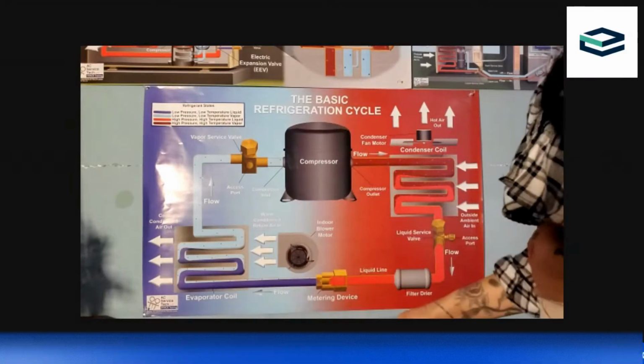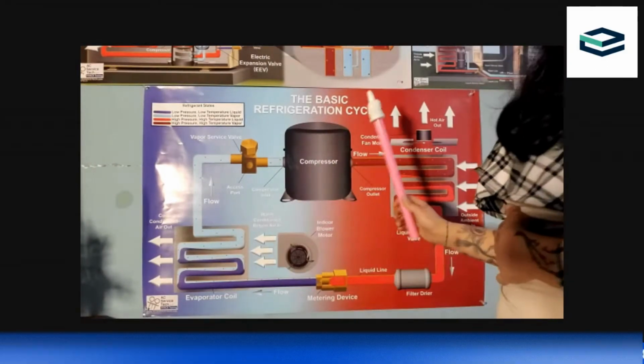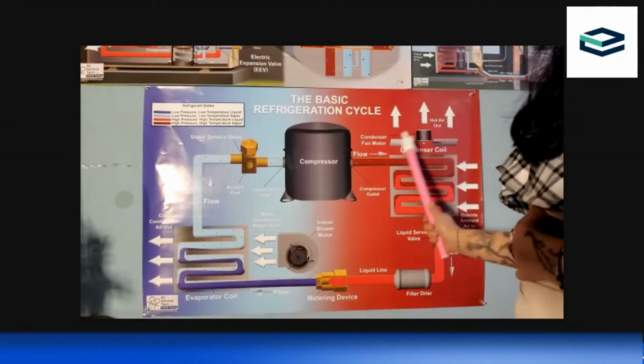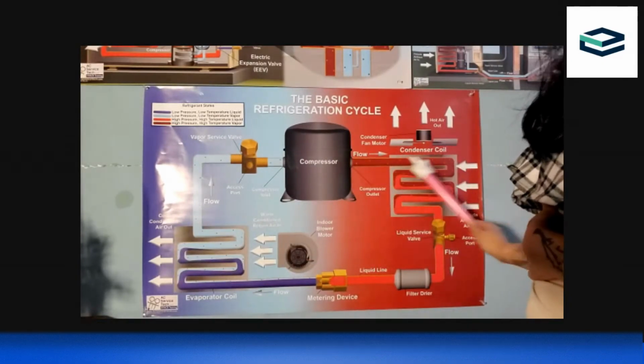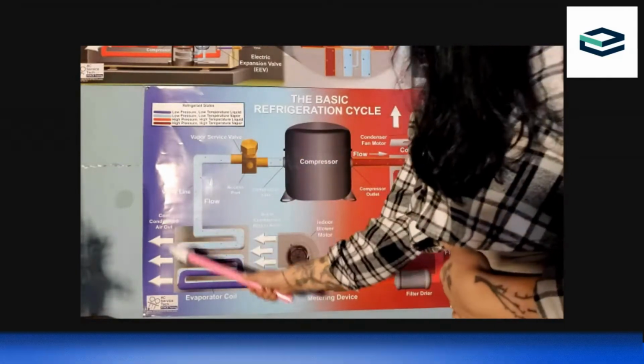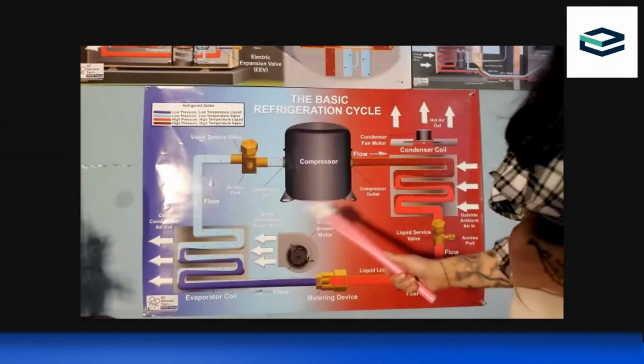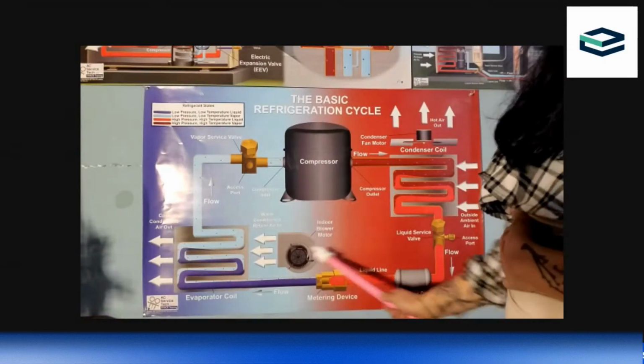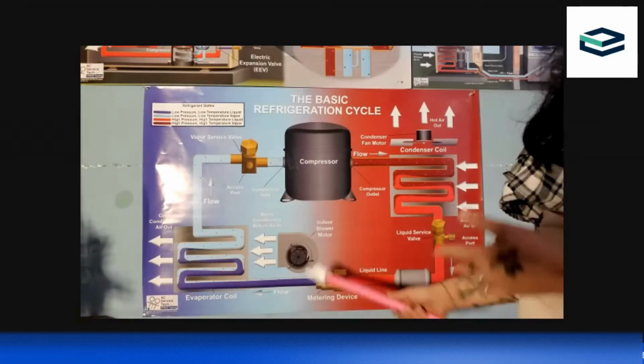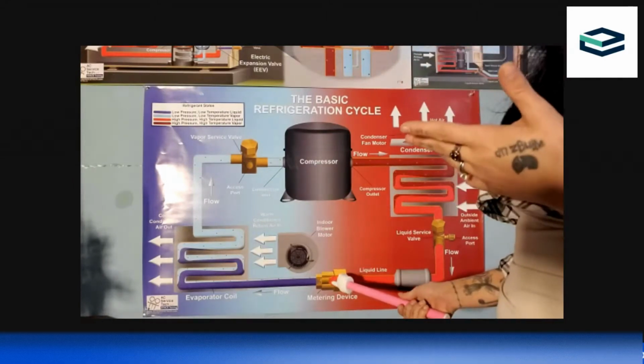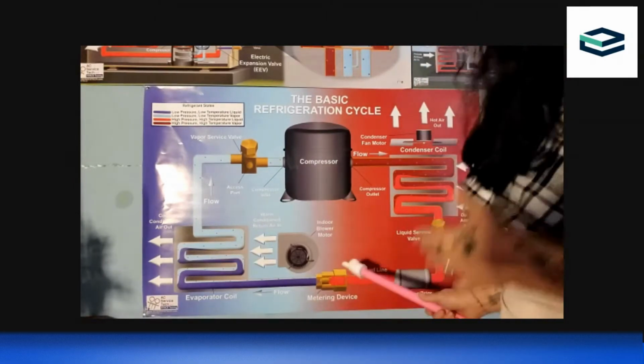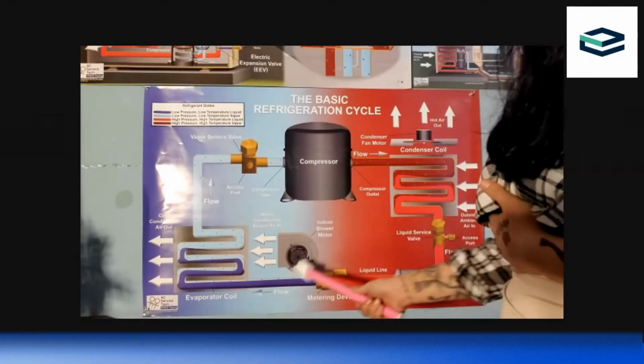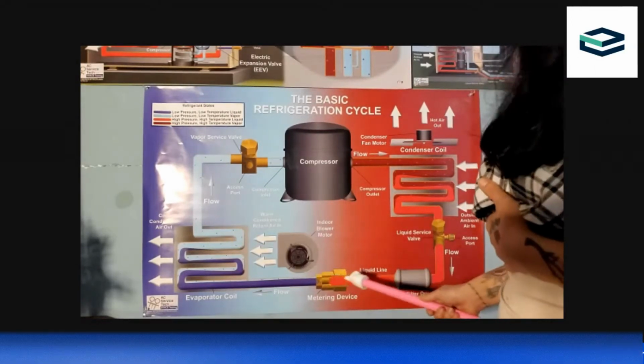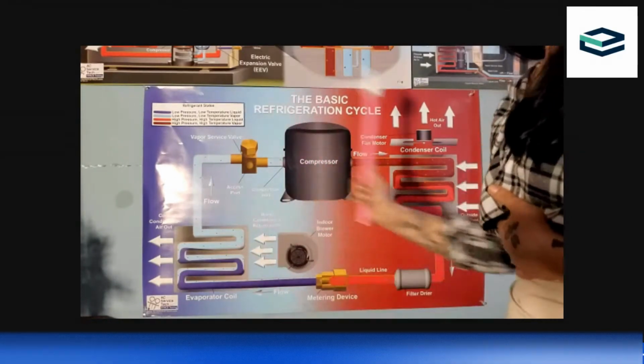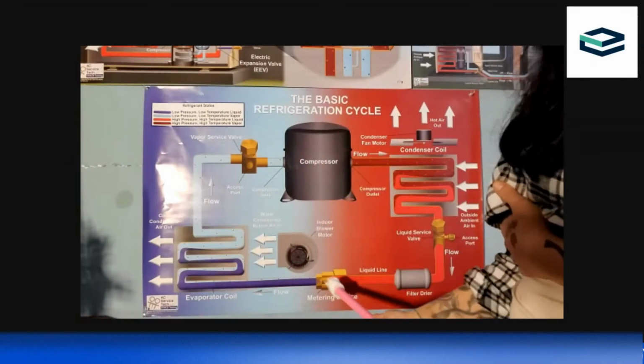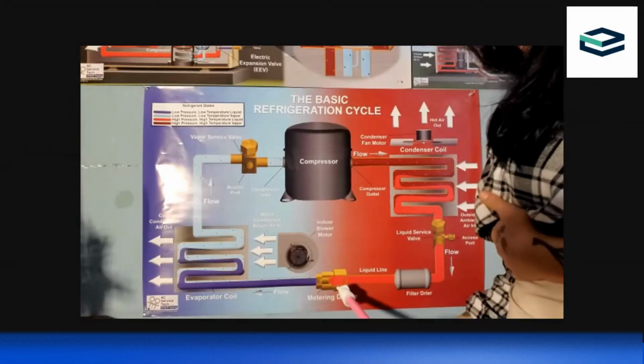So those are important. If we have a very, very high liquid or very, very low liquid saturation, we could have too much liquid in one side. If we have very, very low vapor saturation, we could have too much vapor on one side, meaning there's a liquid line restriction. So this metering device, you'll see a TXV sometimes, but all metering devices clog. Sometimes they go bad. And when they go bad, the number one thing that happens is a restriction in this part of the system. So as I said, it's a circle. We've got to be able to keep going around and around and around. And when we have something wrong with this spot right here, it stops that cycle.